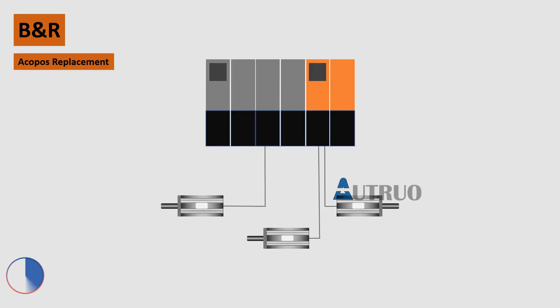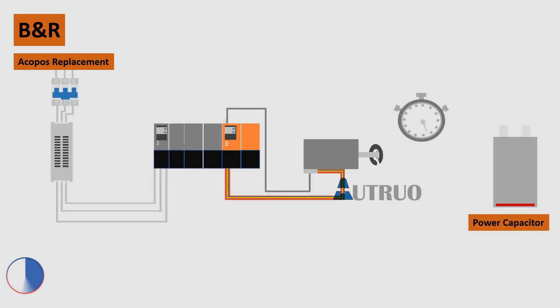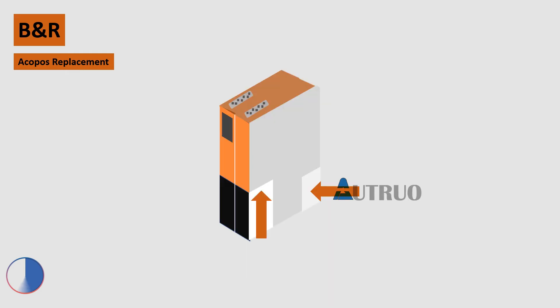Now let's look at the correct steps to be taken when replacing a B&R ACOPOS drive. First, disconnect the power going to the power module and wait until the drive's capacitors have been fully discharged. Remove the faulty drive from the bus bar. The connecting port is designed in such a way that fingers cannot go in between, but to be on the safe side, always wait a few minutes for the power capacitor to fully discharge before you remove the drive.